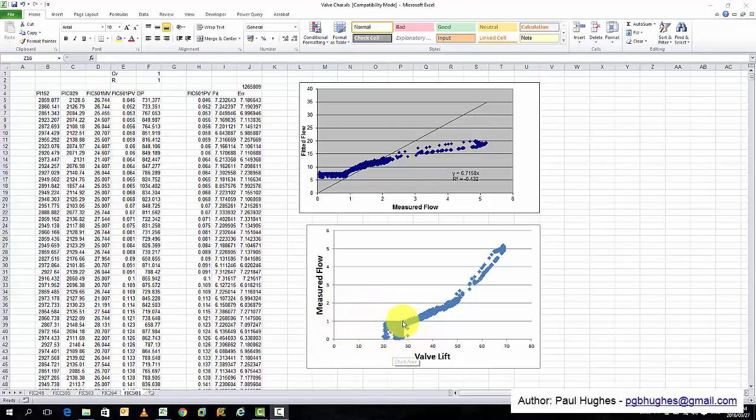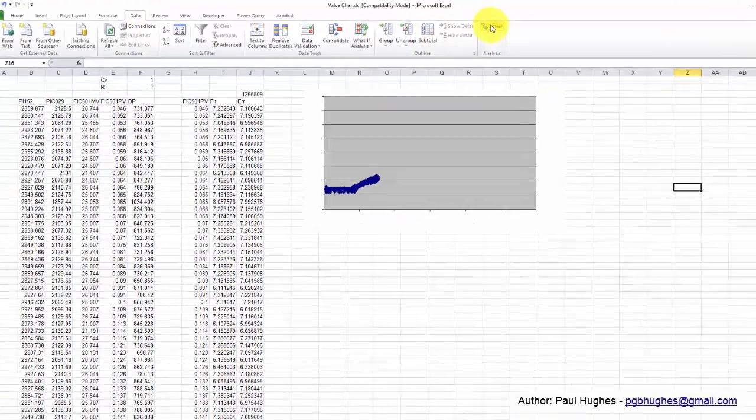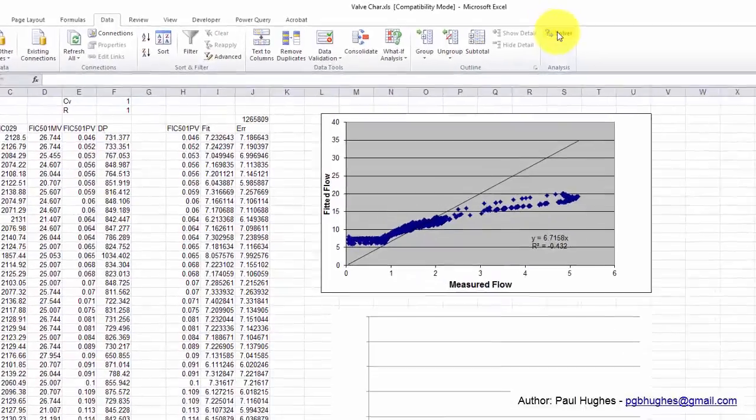This is where we don't know what the flow is like. So using solver, one can use the equation that I had previously, and you're trying to minimize the sum of the square of the errors, which is, here's the actual measurement, and there's the curve fitted measurement.